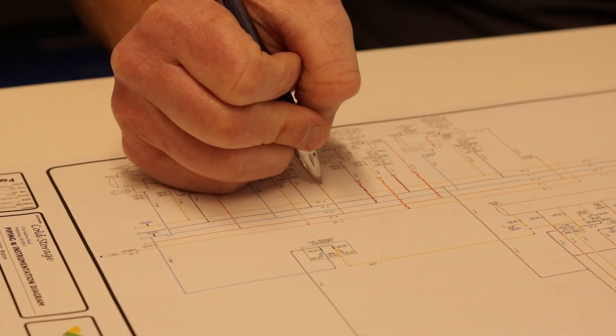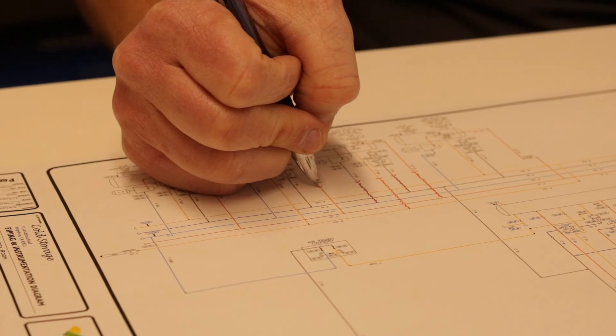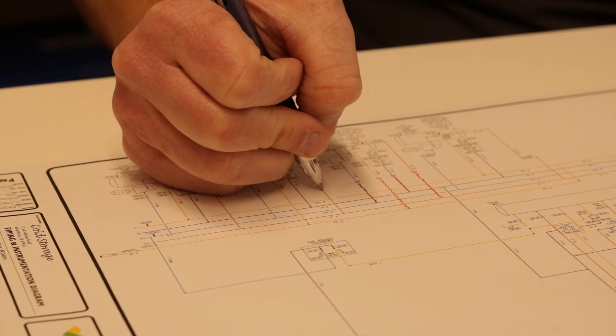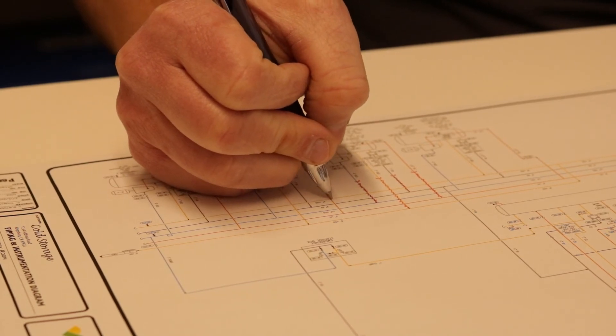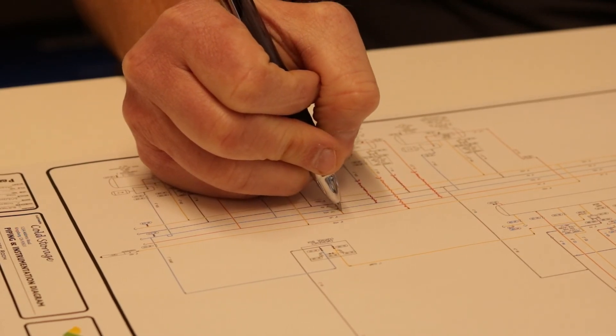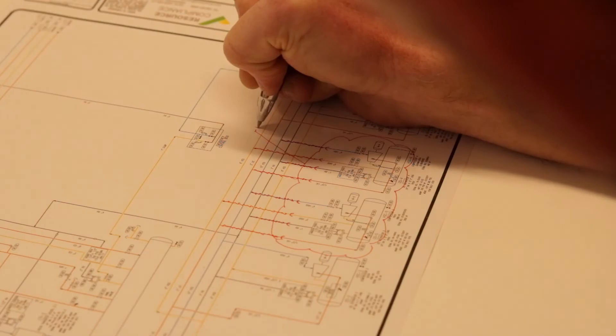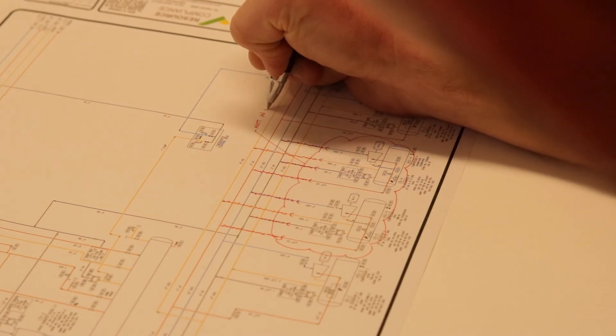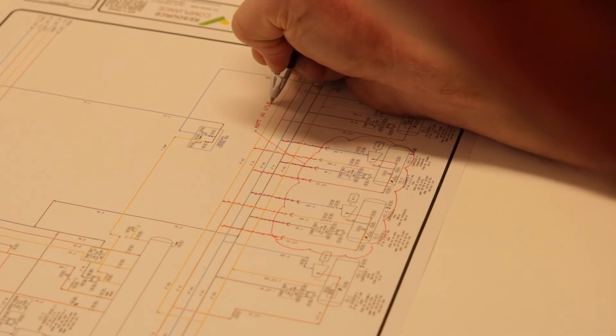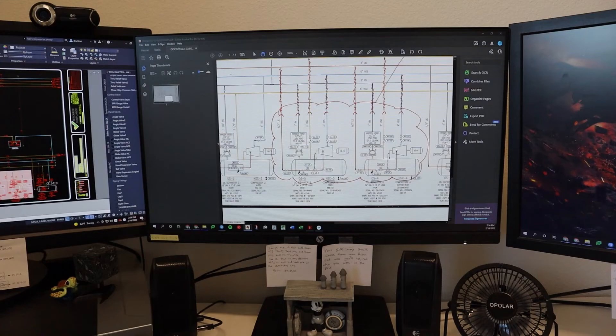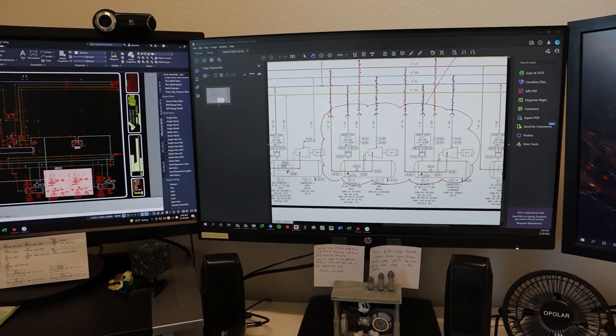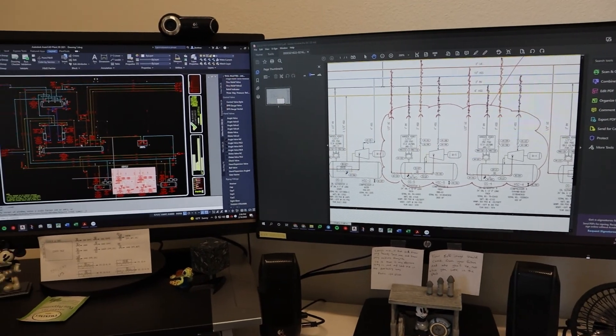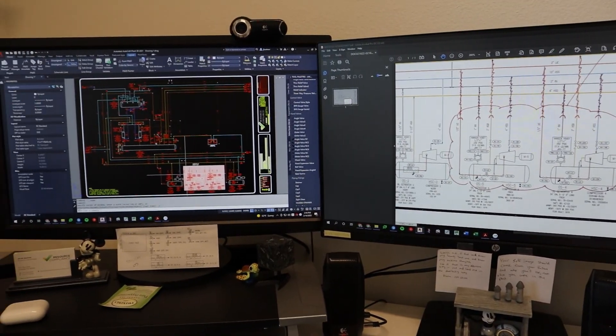Prior to implementing changes, it may be prudent to redline the existing P&ID by hand with a red pen. This method of depicting alterations is particularly effective for smaller changes to process piping and equipment. After the project is completed, the redline P&ID should be audited so that the as-built drawings can be finalized using AutoCAD.